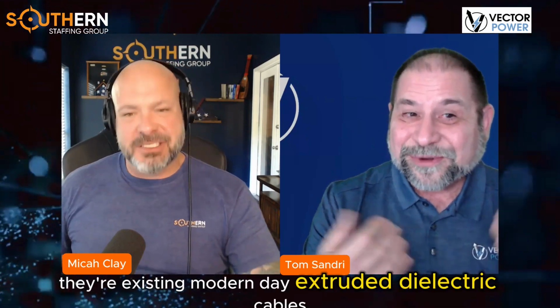What drove bringing DC back was solar farms—they're using modern day extruded dielectric cables that carry DC. So dot 5 doesn't say it's fine to test service-aged cables with DC again. Dot 5 basically says if you're using extruded dielectrics designed to carry DC, here are the testing recommendations.